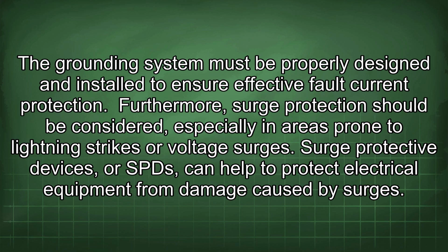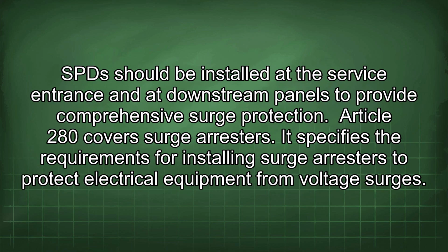Furthermore, surge protection should be considered, especially in areas prone to lightning strikes or voltage surges. Surge protective devices, or SPDs, can help to protect electrical equipment from damage caused by surges. SPDs should be installed at the service entrance and at downstream panels to provide comprehensive surge protection.